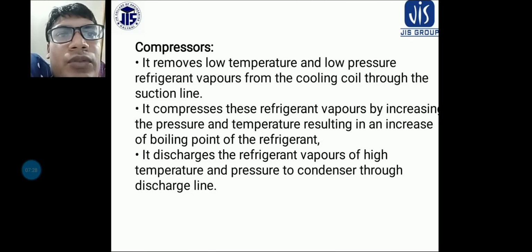Okay, so the compressor removes the low temperature and low pressure refrigerant vapor from the cooling coil through the suction line, and it compresses this refrigerant vapor by increasing the pressure and temperature, resulting in an increase of boiling point of the refrigerant. And next point, it discharges the refrigerant vapor of high temperature and pressure to the condenser through the discharge line.